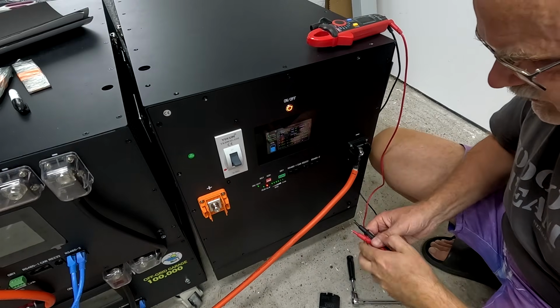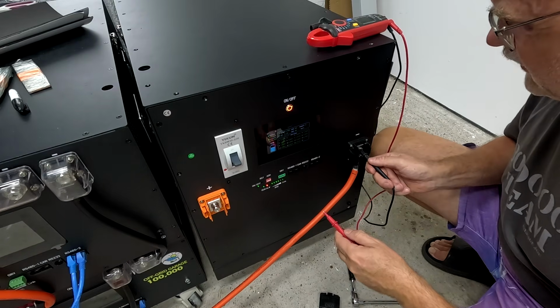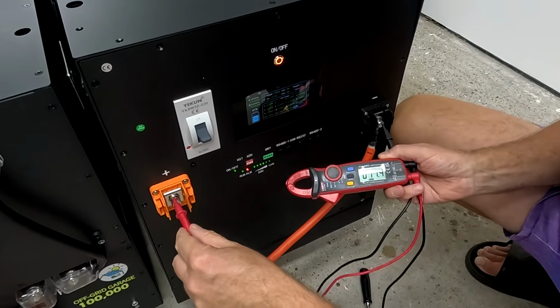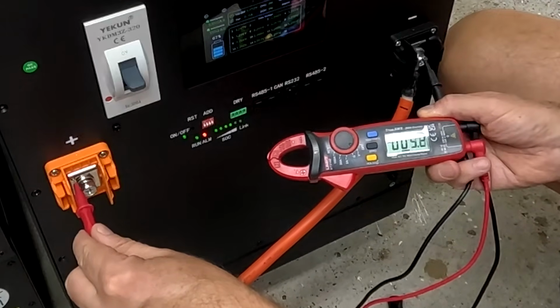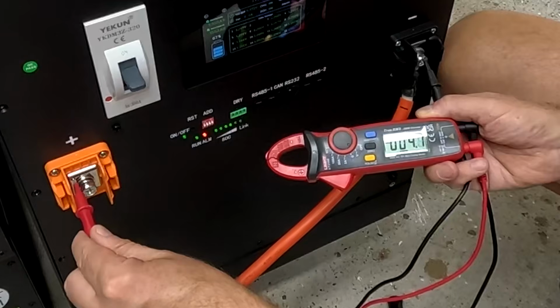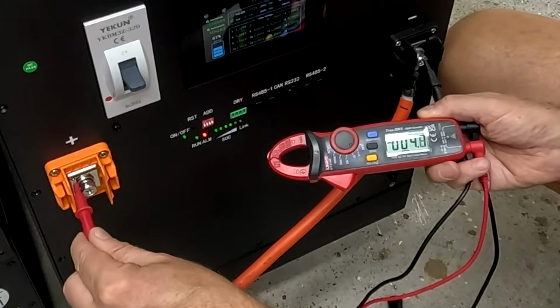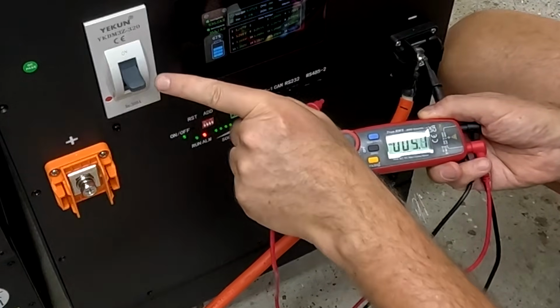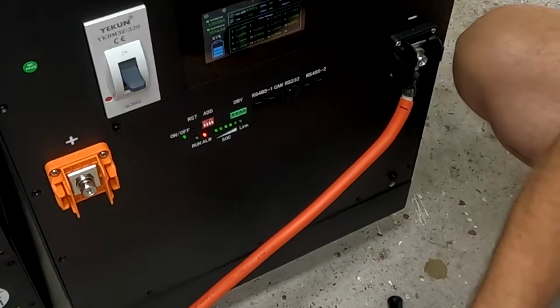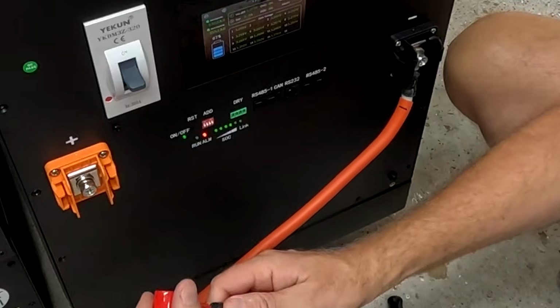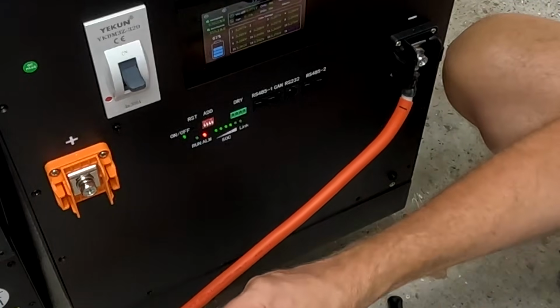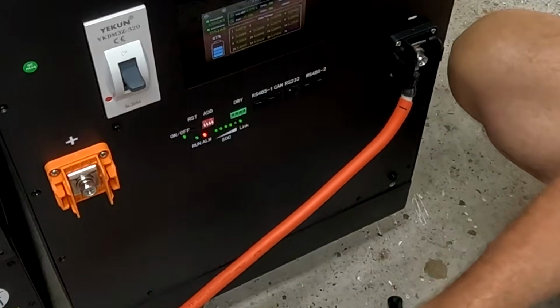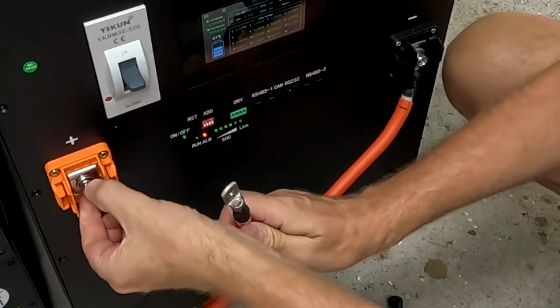Alright, I've connected the negative already, and I just want to make sure there's no voltage here on the terminal before I connect the positive, because these cables are already live connected to the 48 volt bus bar, but there's no voltage because the breaker is still in trip position. But it's better to double check before you connect the cable, otherwise you get a big spark, because there's already current going into the battery then, and we certainly don't want that, not without our permission.